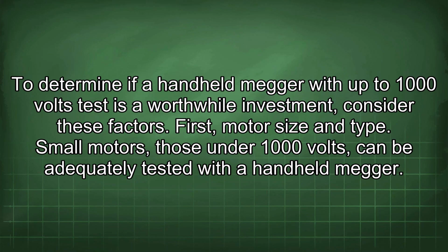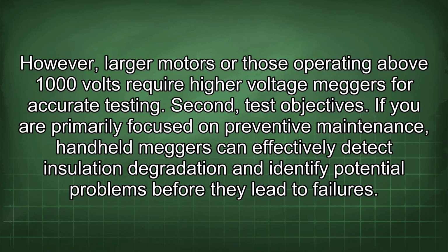To determine if a handheld Megger with up to 1000 volts test is a worthwhile investment, consider these factors. First, motor size and type. Small motors, those under 1000 volts, can be adequately tested with a handheld Megger. However, larger motors or those operating above 1000 volts require higher voltage Meggers for accurate testing.